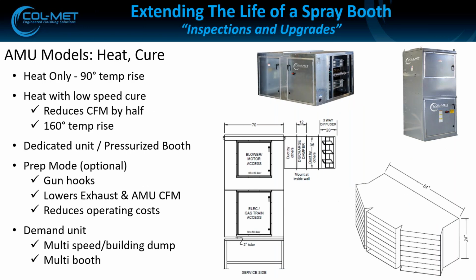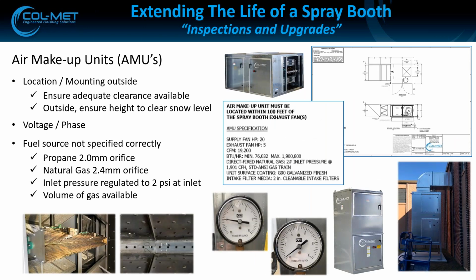We talked a little bit about the discharge units already. There's prep mode, things like this that are really a lot of upgrades for your booth. A gun hook - you don't think about it, but let's say you're painting something and you have a lot of prep time or some inspection time. Well, your booth just sits there and runs wide open while all that's happening. We can integrate gun hooks into our system where when your painters hang their guns, the booth goes into an economy mode or a prep mode. Airflow slows way down, and as soon as the gun picks up, it ramps back up and it's ready to go. That's a pretty neat option when it comes to upgrades for your unit.